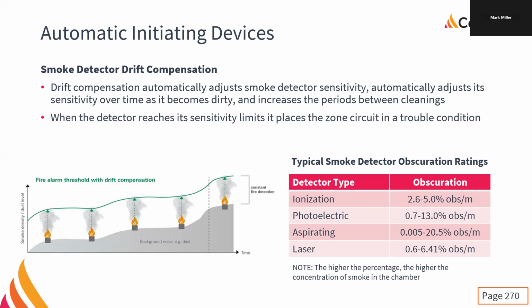So, smoke detector drift compensation. In the addressable world, this stuff does a really, really good job. In the conventional world, it's pretty good, but not great because of limited processing power, but also limited communication abilities. On a Simplex addressable system, if you have a photoelectric smoke detector that gets too dirty and has to be changed, you get a trouble on the panel, and you go to it, and it tells you, photo detector, this address, this location, excessively dirty. There's no guesswork involved. It's too dirty, change it out, right? And all the other manufacturers have similar things. I really like the Simplex one because excessively dirty, that's just poetic.